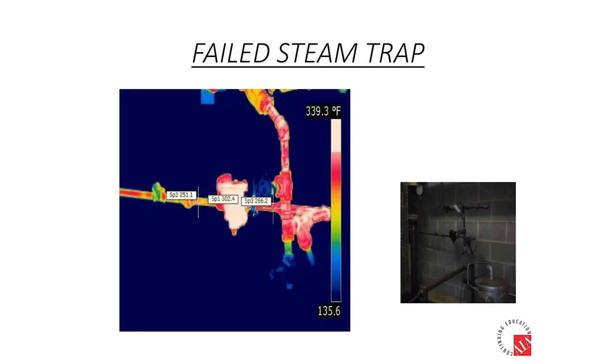In the infrared camera, you can take the infrared picture in any palette you want, black and white, iron, rainbow, and in your office, in the software, you can change the palette. So if you like a lot of different colors, you can use the rainbow palette. To be simple, sometimes I'll convert it to black and white. If the temperature differentiations are very stark, sometimes the black and white. And black and white is a lot easier to focus. The rainbow is very, very difficult to focus. That's one of the things that I really had difficulty with when I first started was simply focusing.